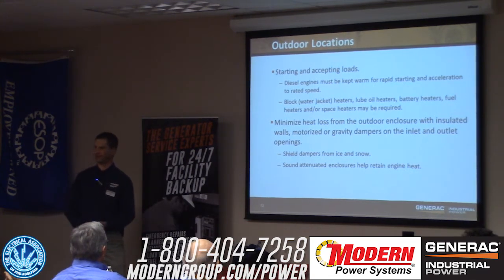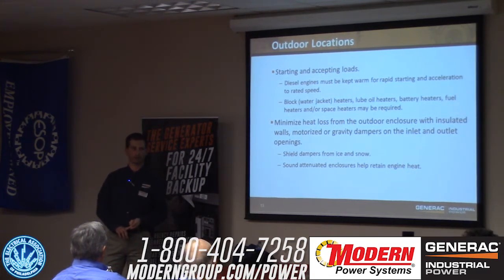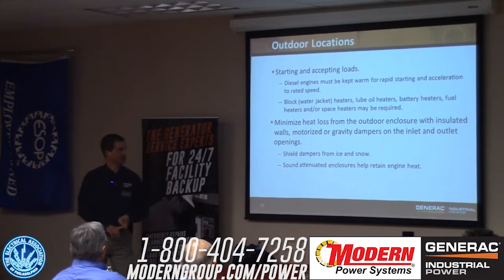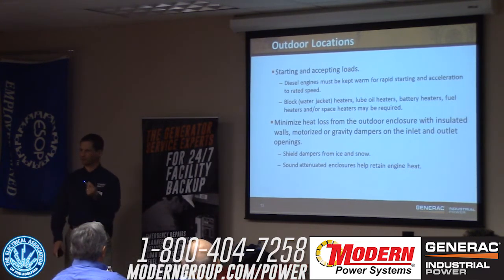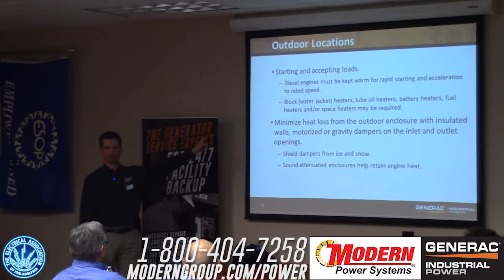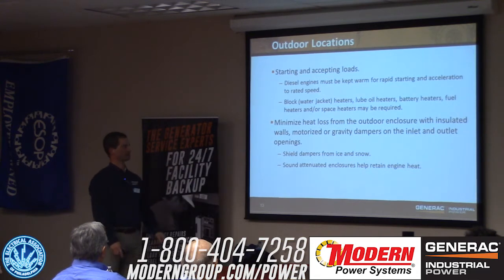Typically that includes, at a minimum, a block heater. Sometimes lube oil heaters, although we discourage them because they tend to locally heat the oil, and you can actually start breaking it down since the probe gets so hot locally. Typically, a block heater is all you need in this part of the country.